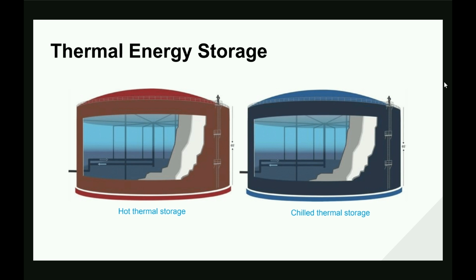But how you fix that is by putting some thermal storage in. At the Roche project in New Jersey, we used the fire tank as a hot water thermal storage tank, 300,000 gallons. It takes about 8 hours for that centrifugal to sit there at 80% loaded, but the peak performance of that machine charges that tank overnight. So there are different ways you can use these different centrifugals, figure out the optimum efficiency point, and make sure you run at that.